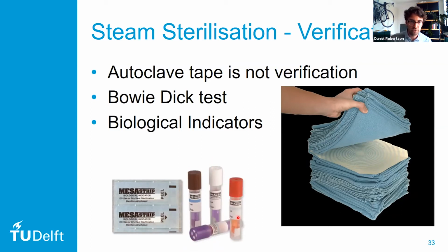Now, these biological indicators consist of a fluid, and they contain bacterial spores. You put these in the autoclave inside of the instrument basket, and this is one of the most reliable ways of checking whether all of the microbes have been killed, because if after sterilization these devices turn color, you know that the bacterial spores in these biological indicators have died as well. So it's a very good method of showing that the steam sterilization was successful.